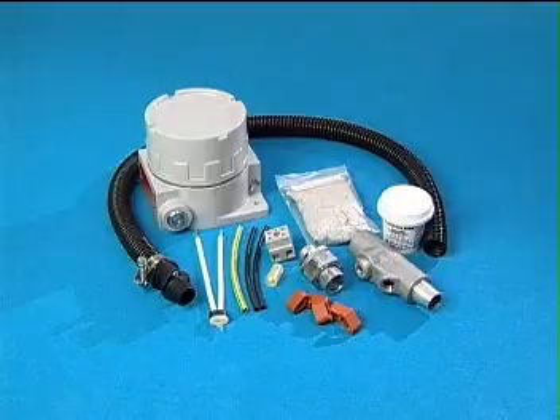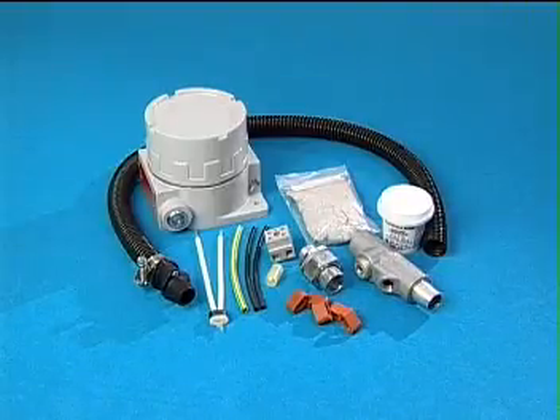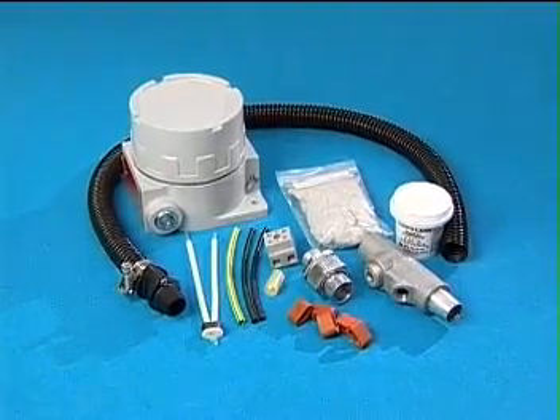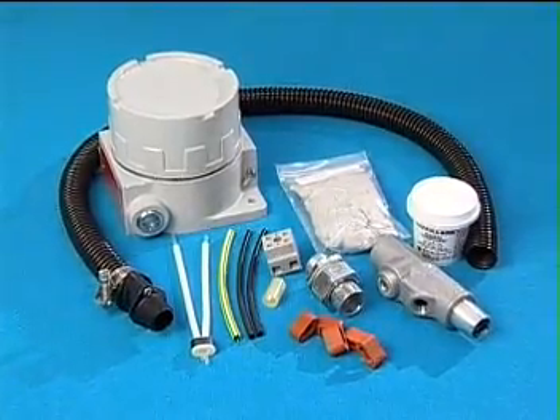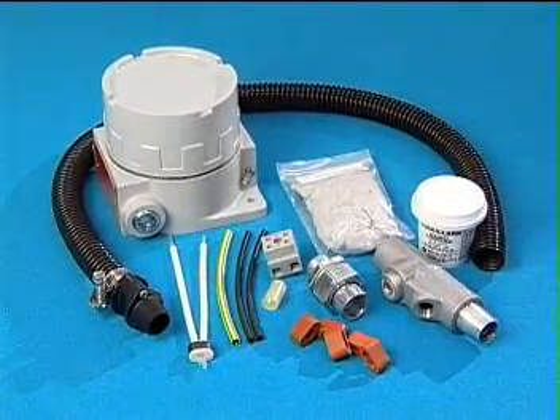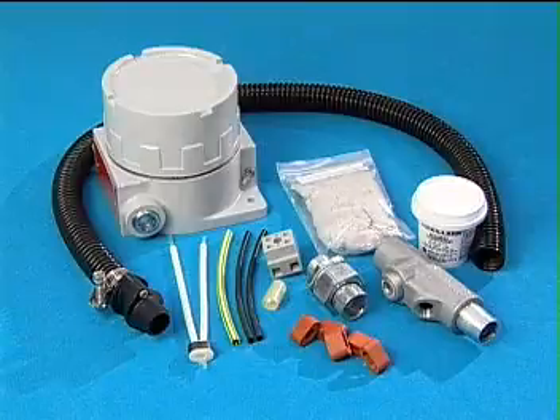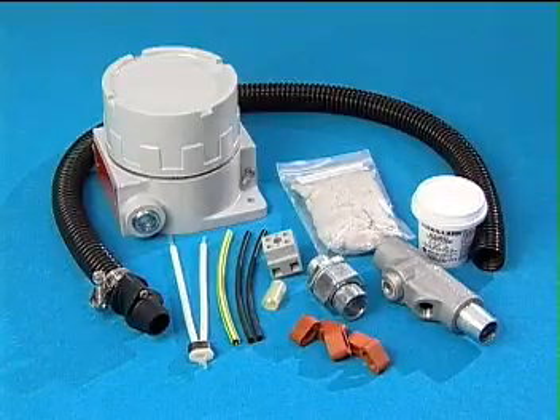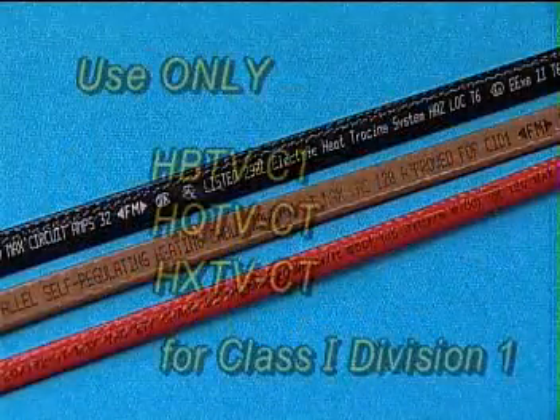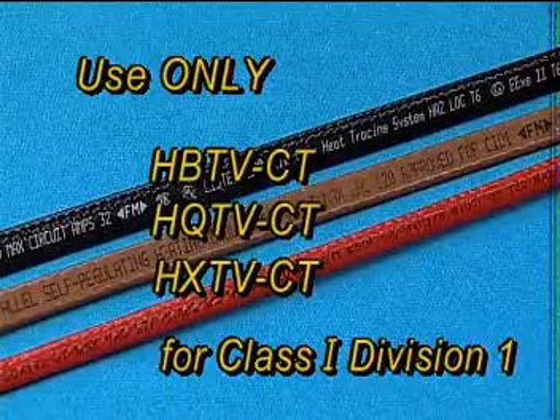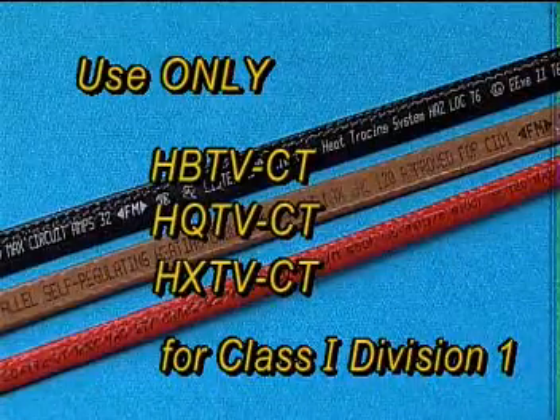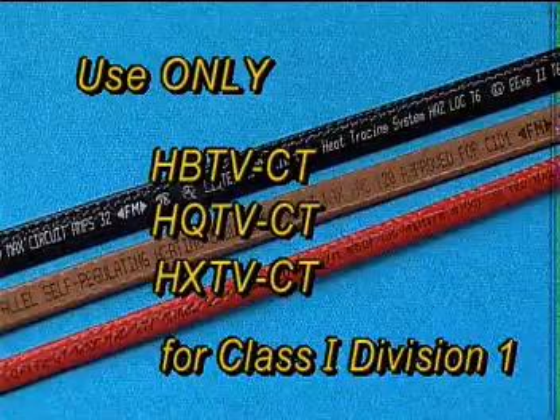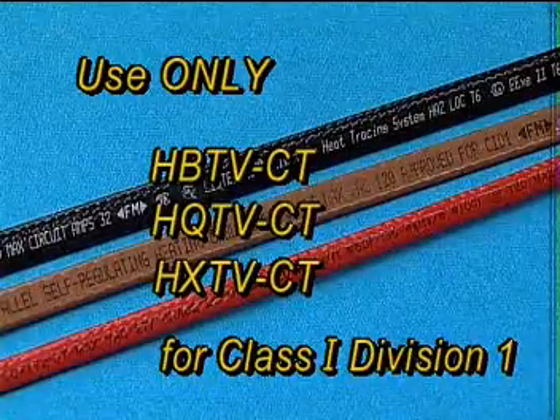There are special considerations for installations in Class 1 Division 1 areas. Explosion-proof power connections, splices, T's, and end seals are required, and these components are installed differently than ordinary area or Class 1 Division 2 components. In the U.S., only HBTVCT, HQTVCT, and HXTVCT cables should be used in Class 1 Division 1 locations.